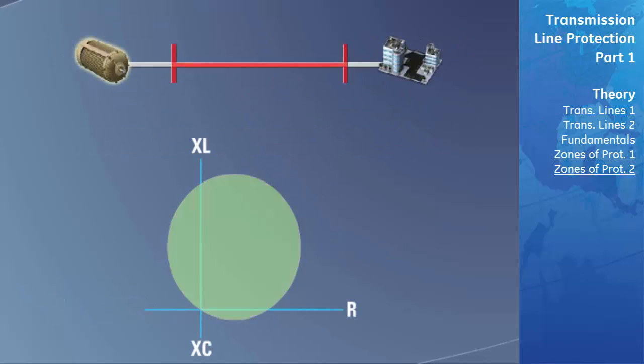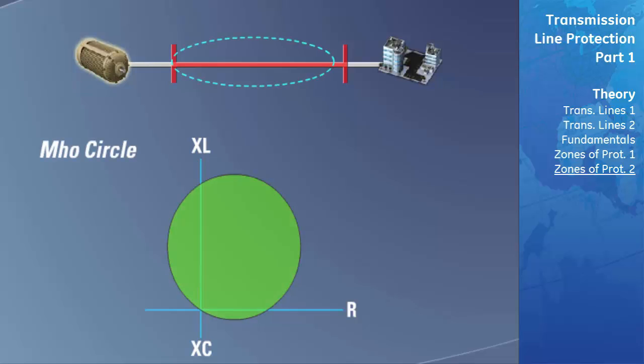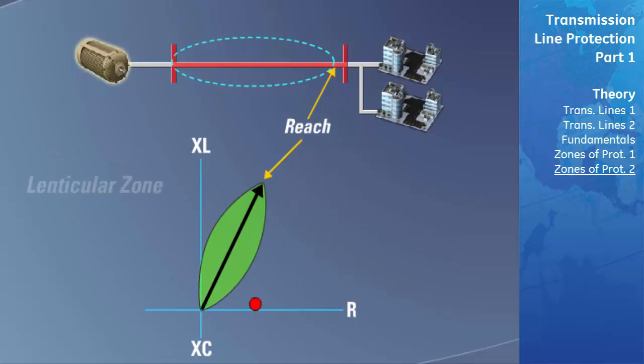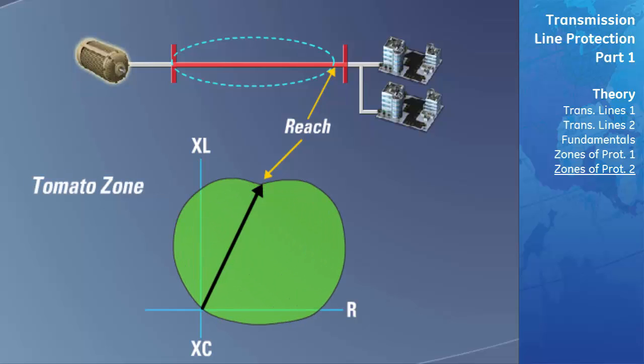Advanced microprocessor-based relays such as the UR D60 give the user the ability to further customize the shape of the Mho circle to meet their protection needs. For example, if this power system has instances where it can be heavily loaded, which may cause the impedance of the line to encroach into the Mho circle, the area of the circle may need to be changed to not include this area in the zone of protection. The Mho zone can be altered to form a lenticular shape which looks at the magnitude of the impedance and only allows tripping when the impedance falls very close to the angle of the transmission line impedance. Therefore, highly loaded systems which cause the impedance point to approach very near the origin will not result in tripping the transmission line. The D60 relay also gives the protection engineer the ability to configure the Mho characteristic into what is known as a tomato-shaped zone. A tomato-shaped Mho characteristic allows for faults that have more of a resistive element to fall into its zone of protection.